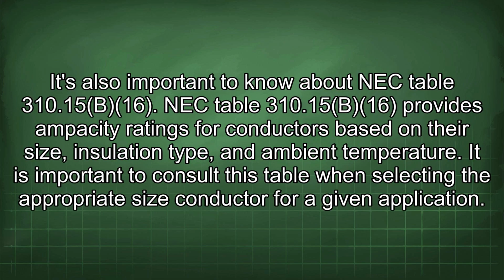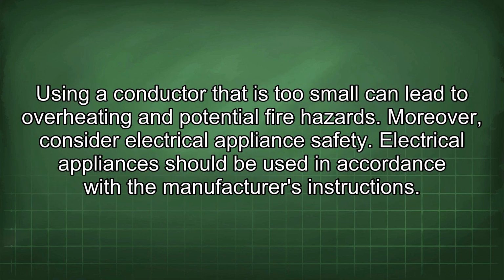It's also important to know about NEC Table 310.15(B)(16). NEC Table 310.15(B)(16) provides ampacity ratings for conductors based on their size, insulation type, and ambient temperature. It is important to consult this table when selecting the appropriate size conductor for a given application. Using a conductor that is too small can lead to overheating and potential fire hazards.